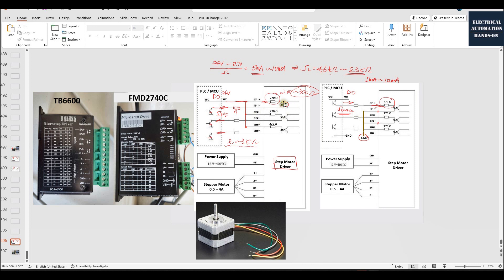The left side and right side show two different wiring styles. The left side, for the digital output channel, is the current sink style — usually called NPN output. Japanese PLCs commonly use this sink digital output style. But the more common way is the right side: the digital output of the PLC uses the current source. Each channel supplies current from inside to outside. The stepper motor driver side uses a common ground. To limit the current, we use a 2 to 4K ohm resistor when using 24V.